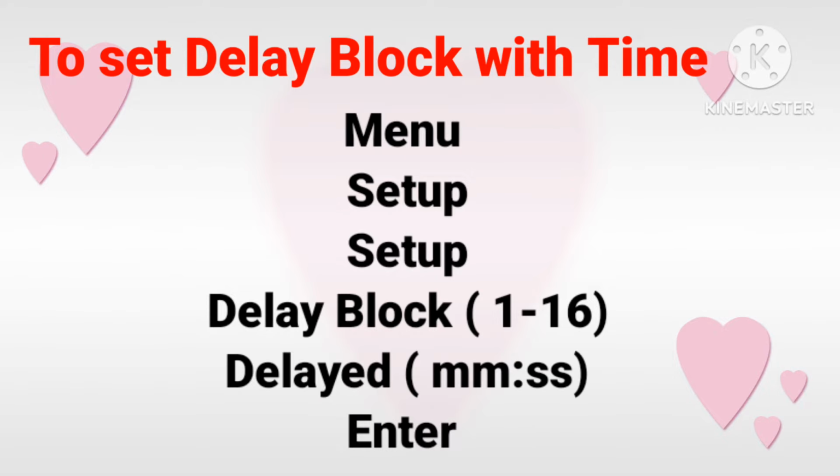If you want to put a delay block time, you have to put a delay time in those particular sectors, like lift or exhaust fan or sounders. First put those devices in the sector, then you go to the time. To set a delay block with time: menu, setup, setup, then delay block.